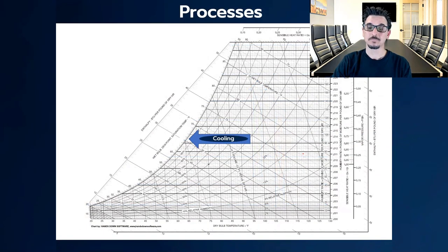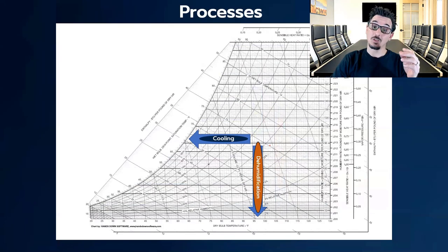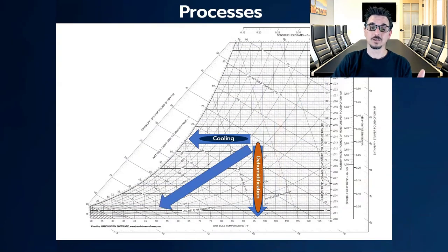Just as a review, cooling is moving in this direction. Dehumidification, we're moving in this direction. So when we go through a cooling coil in an air conditioning system, we're both cooling and dehumidifying and it would look something like this. Anything moving in this direction on the psychrometric chart is a cooling and dehumidification process.